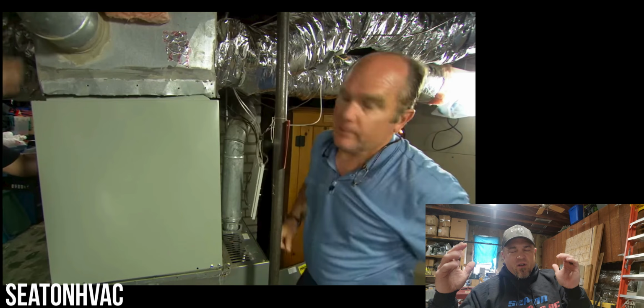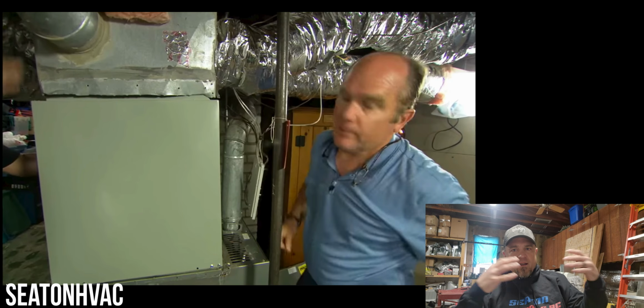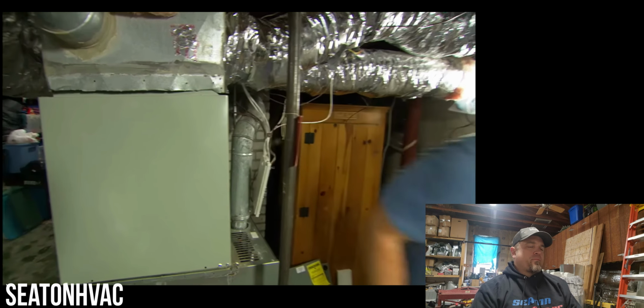What they should have done here on this supply is they should have taken all the runs off and put a nice radius fitting on top, and then just have everything tap off equally, and then add about 12 to 18 inches of duct past your last run for back pressure, and the airflow would be a lot better. Be a lot better on the static too. It'll be good.